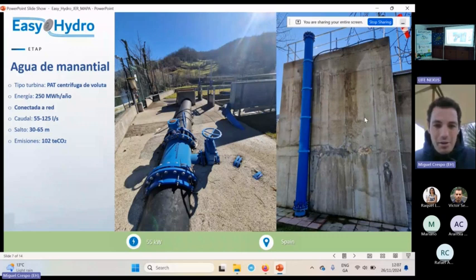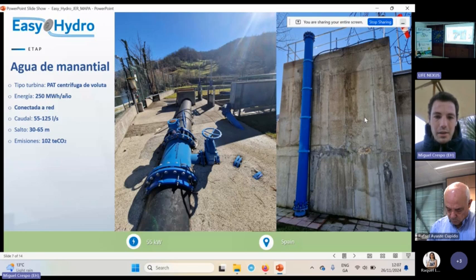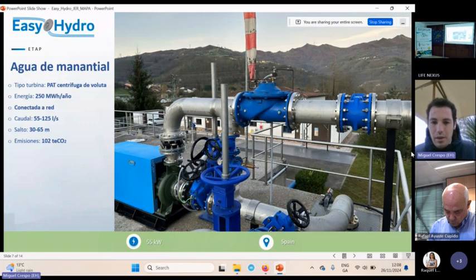So this is somewhere near León. It's in a small town in Asturias. It's a water treatment plant providing water to several villages, and part of the water comes from a spring. So before, it was not possible to discharge into this concrete break pressure tank because of the high pressure. But after collaborating with the operator, we designed this system to basically take advantage of the high elevation difference between the intake and the discharge point.